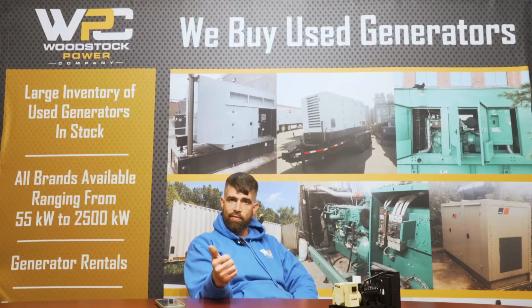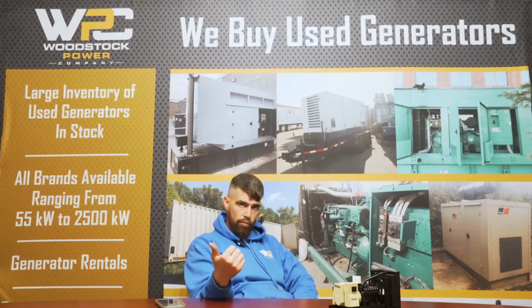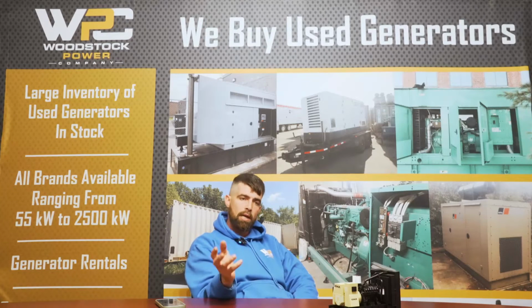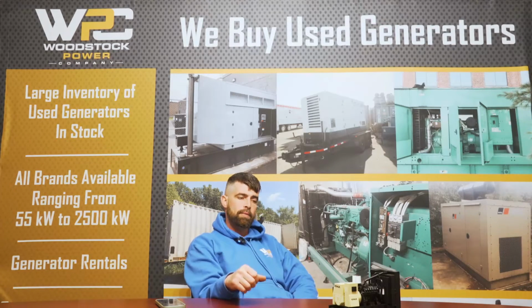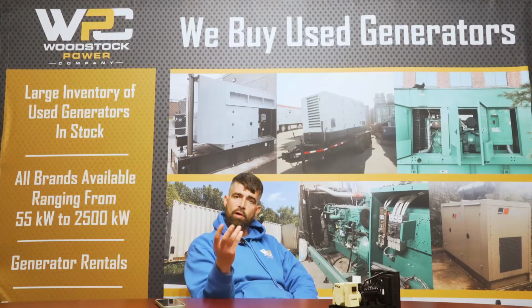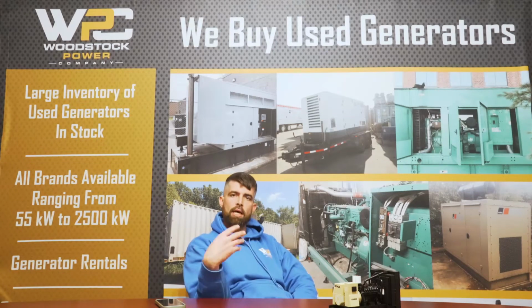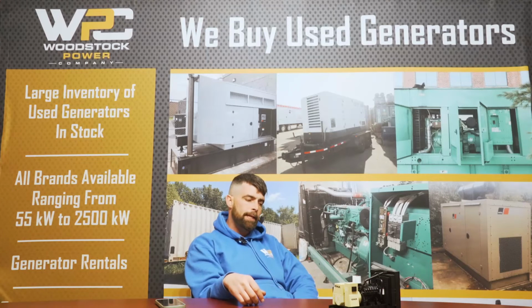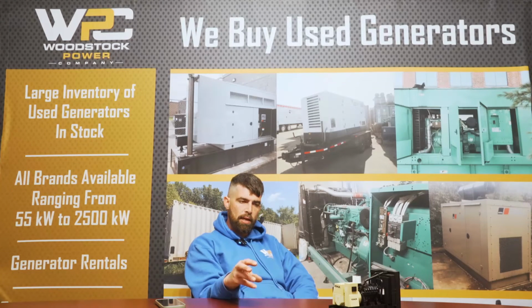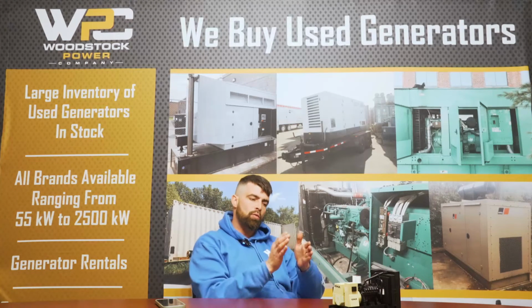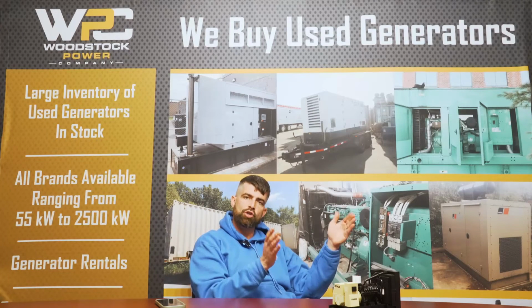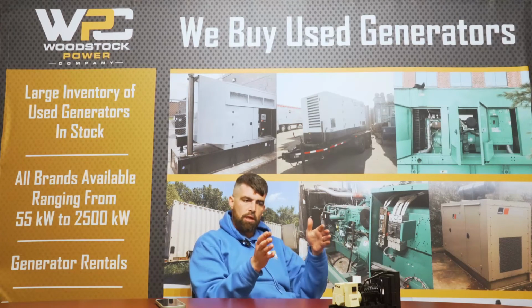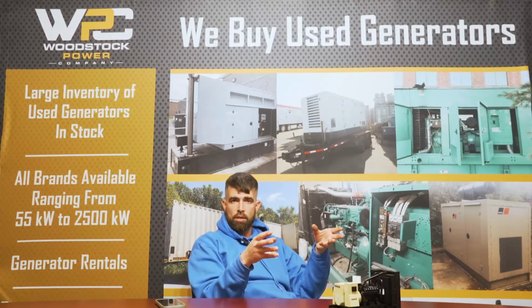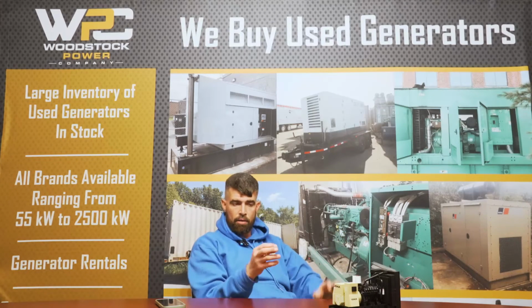So service every 250 hours or so is what we recommend. Load bank every 3 months or so. And obviously your weekly start of the generator, let it run for about 30 minutes. Make sure it gets cycled, make sure it stays healthy. And that should give you a good idea on a weekly to a monthly basis of where your generator is situated and its condition overall inside and out.